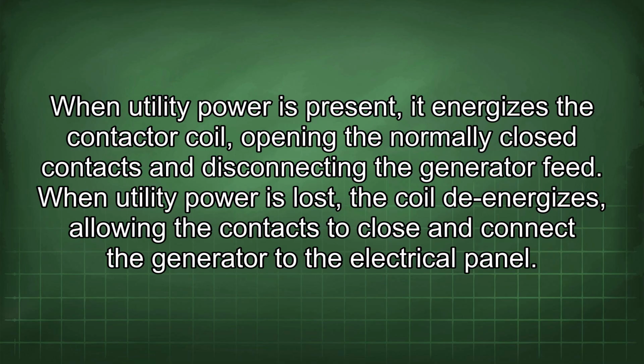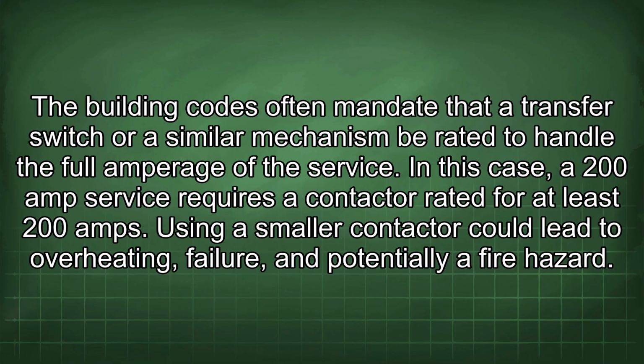When utility power is present, it energizes the contactor coil, opening the normally closed contacts and disconnecting the generator feed. When utility power is lost, the coil de-energizes, allowing the contacts to close and connect the generator to the electrical panel. The building codes often mandate that a transfer switch or a similar mechanism be rated to handle the full amperage of the service. In this case, a 200 amp service requires a contactor rated for at least 200 amps. Using a smaller contactor could lead to overheating, failure, and potentially a fire hazard.